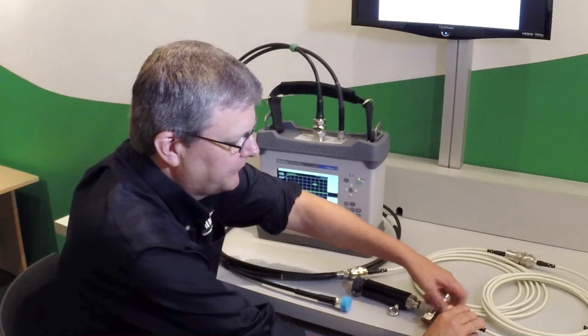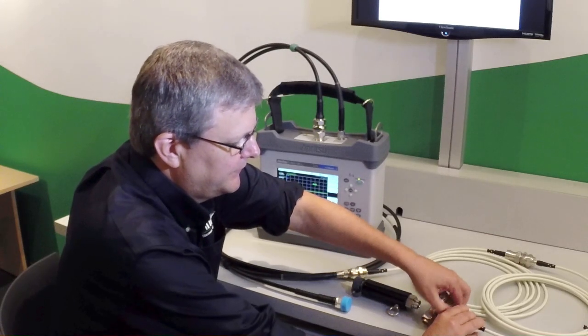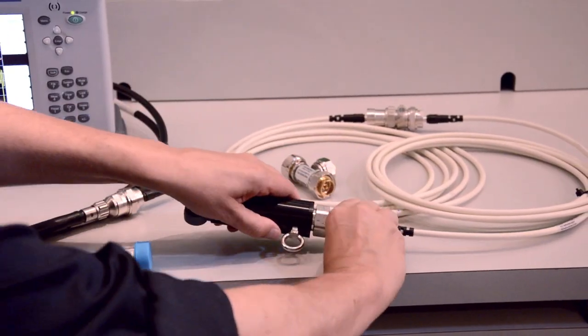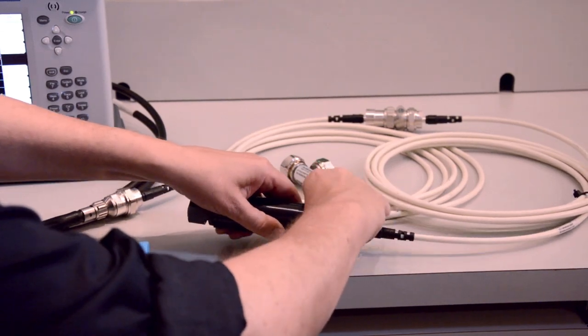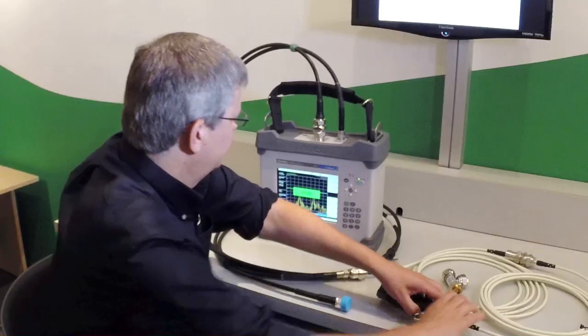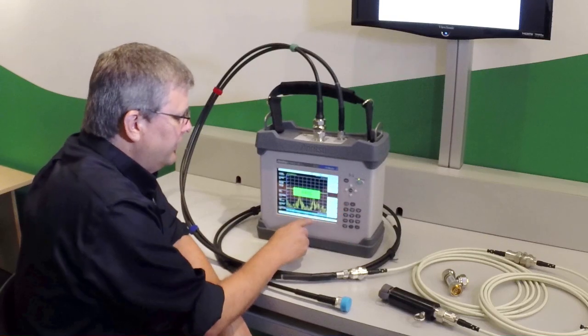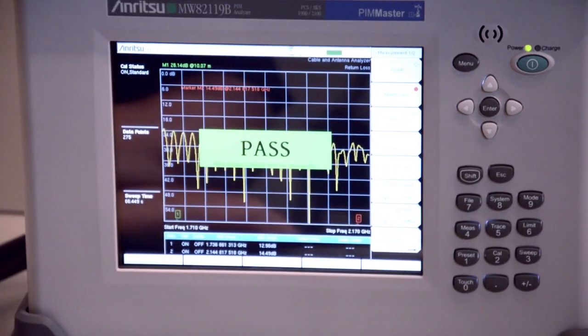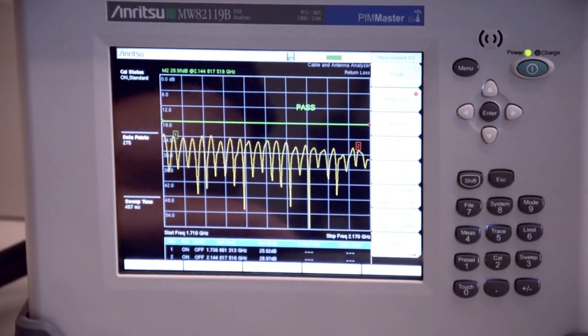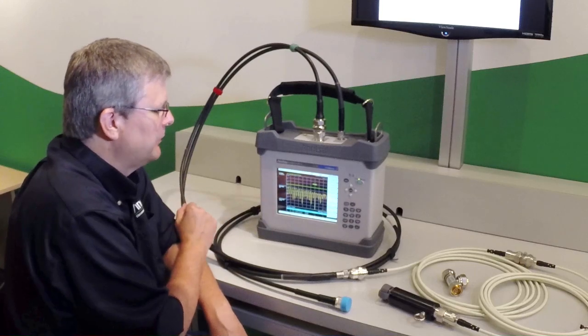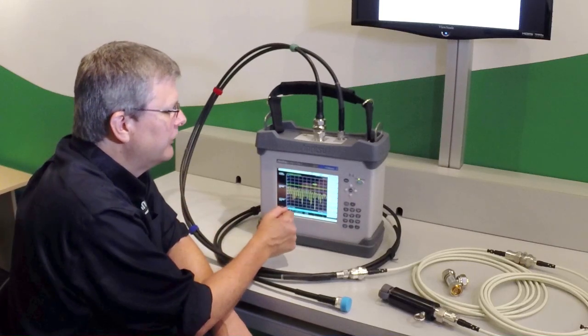The final thing we're going to do is connect the actual antenna, or in this case our low PIM termination, to the end of the line and do final verification measurements. We're going to go into measurements return loss, and once again the return loss of the overall system now looks very good. So this is the measurement we're going to save as the final system measurement.